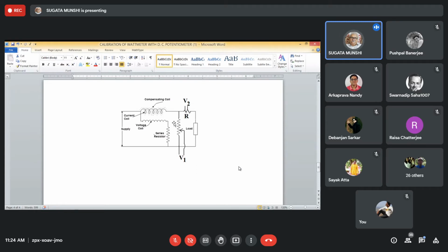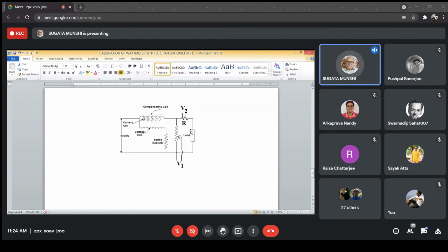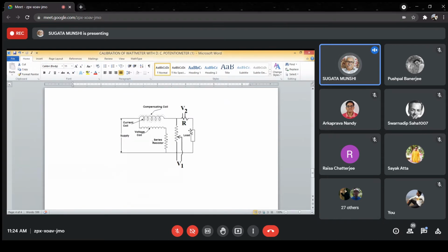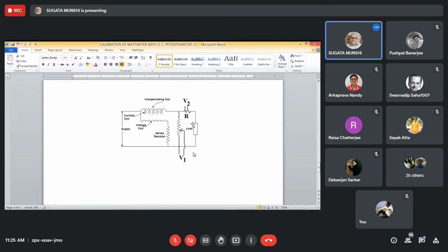And yes, the current coil carries this load current. If you recall the construction and principle of operation of the dynamometer type instrument, you will remember that in dynamometer type instruments there are two fixed coils, two coils fixed in position. Those coils are connected in series, and the series combination is used as the current coil. The movable coil is used as the potential coil. Why is it so? Why don't we do the reverse thing?